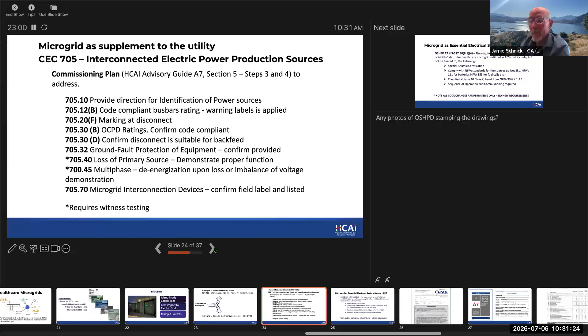The code, language that was put into the national code and adopted by California, says that requirements for a microgrid to serve as an emergency source must be sufficiently reliable for healthcare use. What we identified in the OSHPD CAN is: number one, just like generators, if you're replacing generators with other sources, they need to be specially seismically certified. Number two, they still need to follow the NFPA requirements for that particular source.